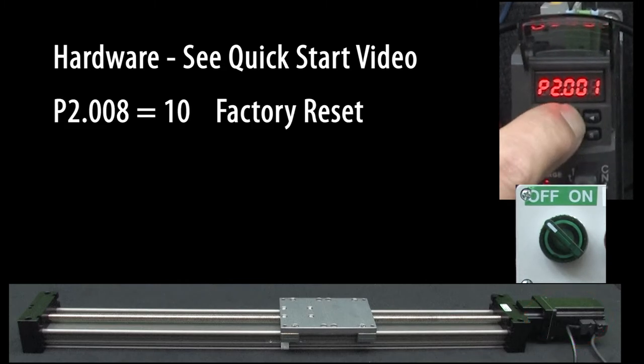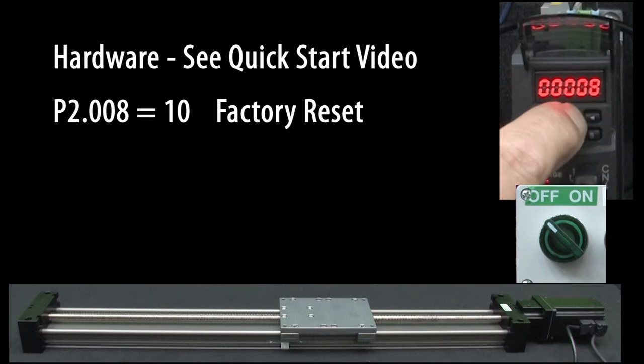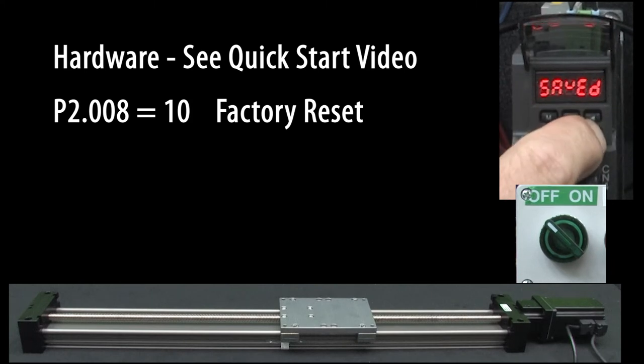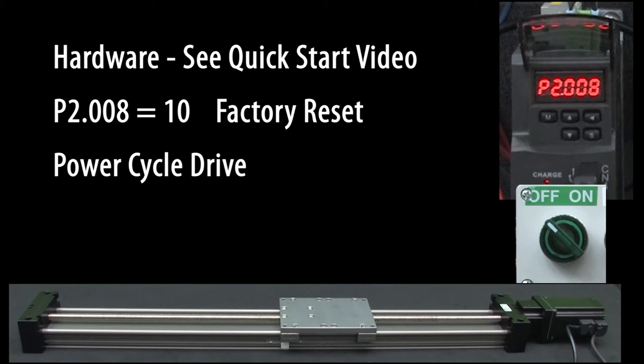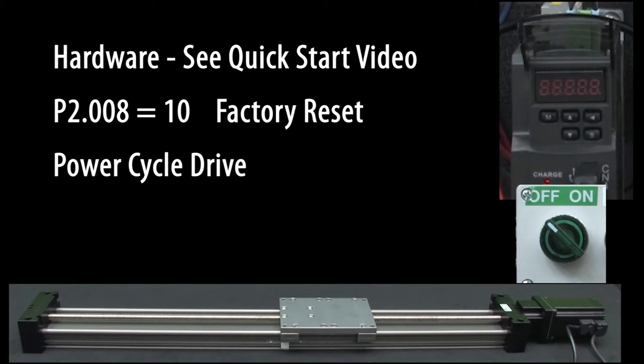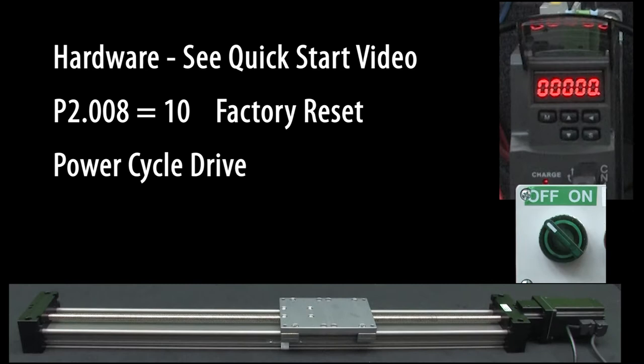I am going to go to parameter 2.008 and enter a 10 to do a factory reset so you know exactly where I am starting from. And we always do a power cycle of the drive after a factory reset just to make sure any residual values get cleared out.